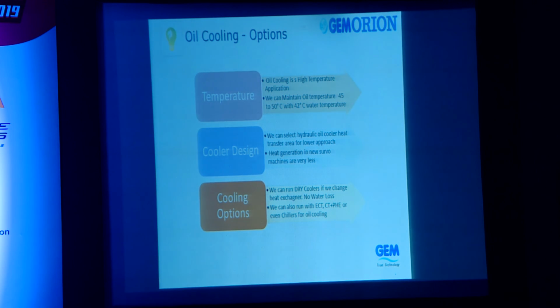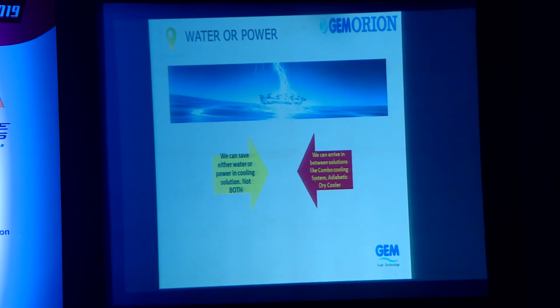So if we run the dry cooling tower, we can change the heat exchanger also. That means no water loss, or we can use an ECT plus PHE combination, or use a chiller for totally avoiding water for the oil cooling application. So the net result is either we talk of water or power. Both are currently two extremes. Of course, now power, at least solar and other sources are coming, but water is becoming very difficult. So the idea is that we should have a via media solution where we can have an optimum solution where we conserve water as well as optimize on power. So that is the idea.